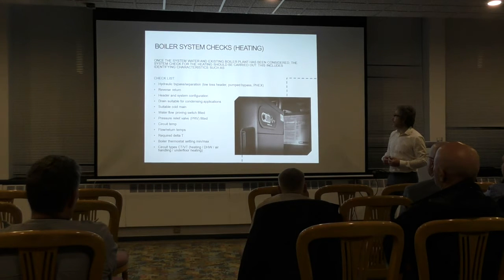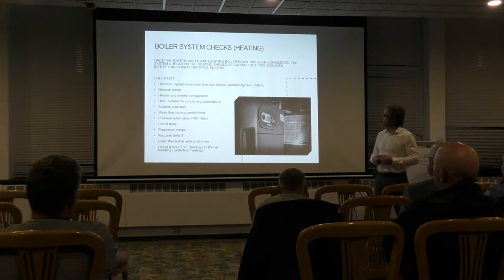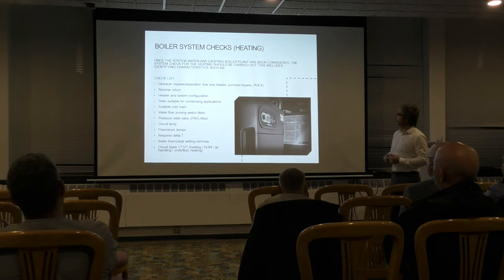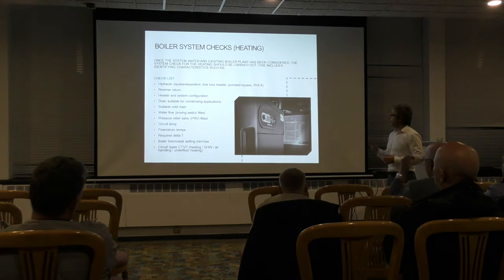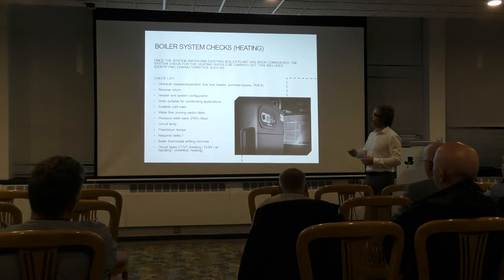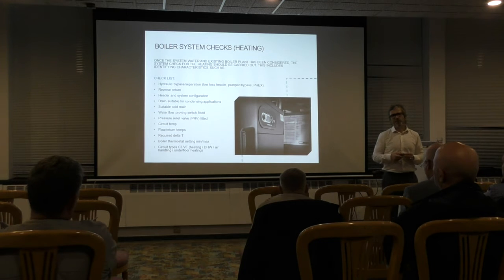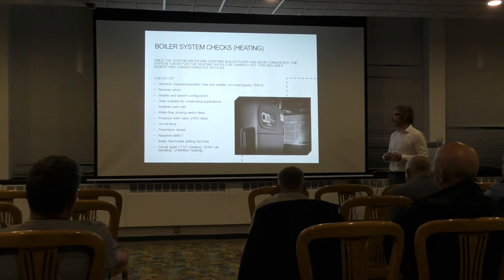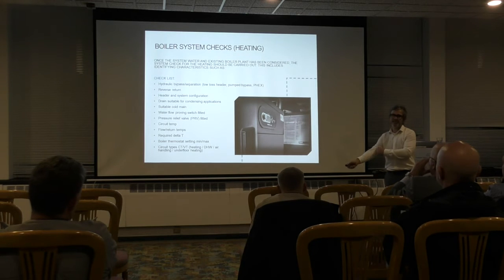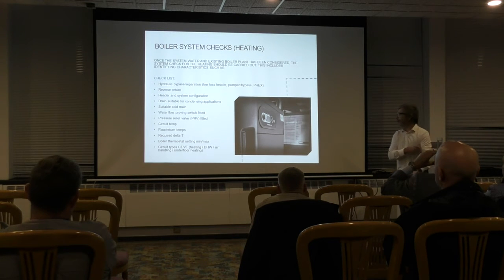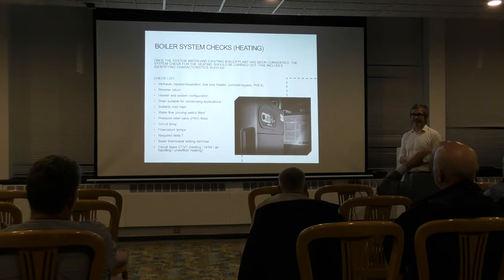And moving on from there, obviously suitable cold main, so we need one of those. Water flow proving switch fitted, is there one? Pressure relief valve. Circuit temperature flow and return temperatures and required delta T. I suppose they almost go hand in hand together. So I think if you're looking at an older system, chances are that system will be maybe 11-degree delta T, sort of 82, 71. Now, if we're putting in condensing boilers, those boilers are never going to condense at 82, 71.